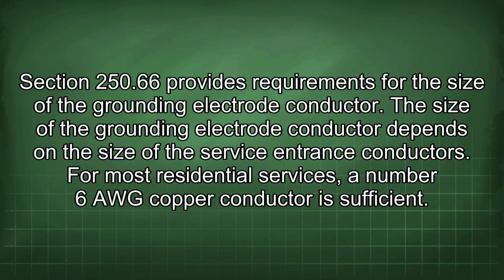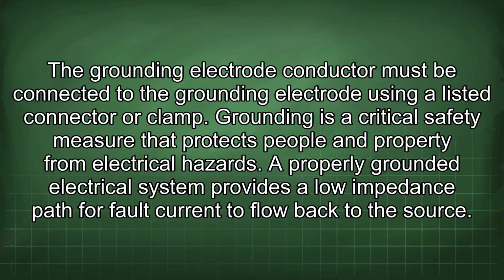The size of the grounding electrode conductor depends on the size of the service entrance conductors. For most residential services, a number 6 AWG copper conductor is sufficient. The grounding electrode conductor must be connected to the grounding electrode using a listed connector or clamp. Grounding is a critical safety measure that protects people and property from electrical hazards.